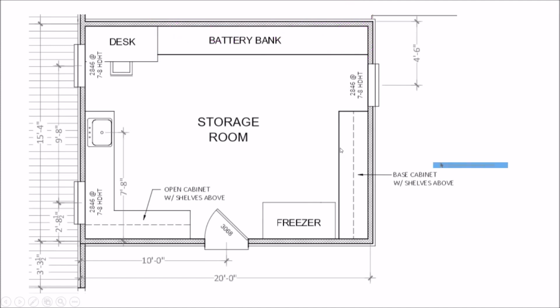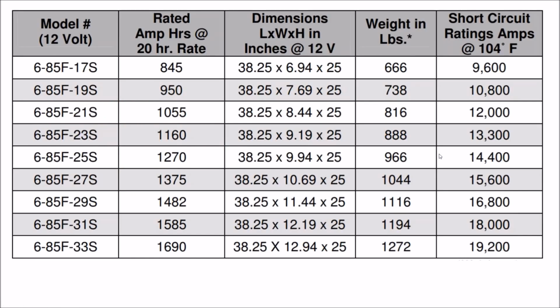The battery dimensions we went with stick out from the wall by about 2 feet, and they're 38 inches tall by 7 inches wide. So these are our batteries: they stick out 2 feet, while our solar equipment sticks out only 6 inches. That means we can't put the solar equipment above the batteries on the wall; they have to be spread out for serviceability.